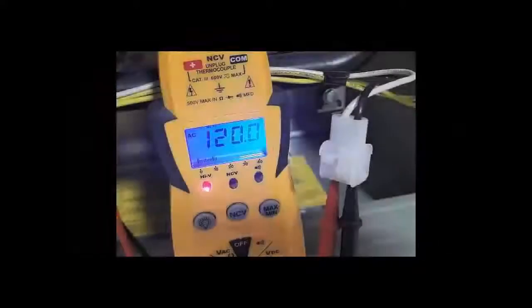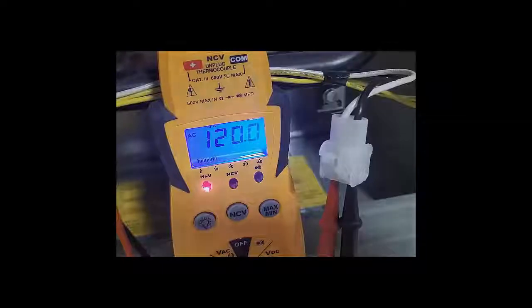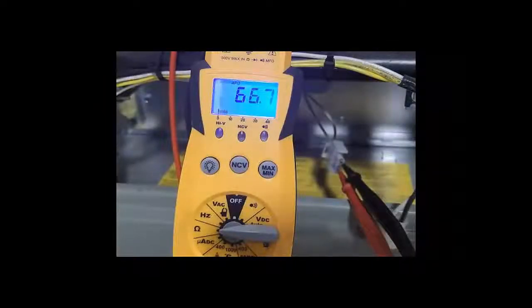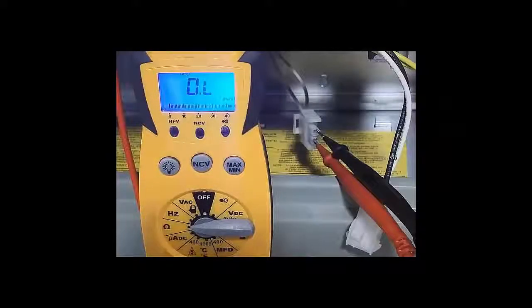If you are getting power to the igniter, but it is not heating up, then the igniter is bad. And you can easily check that by setting your meter to check for ohms and ohming the igniter. You should get a reading of somewhere around 10 to 100 ohms. If you get a reading showing open line or open circuit, the igniter is bad and should be replaced. If you get a reading well over 100 ohms, the igniter may still work, but that is an indication that it is starting to go bad.